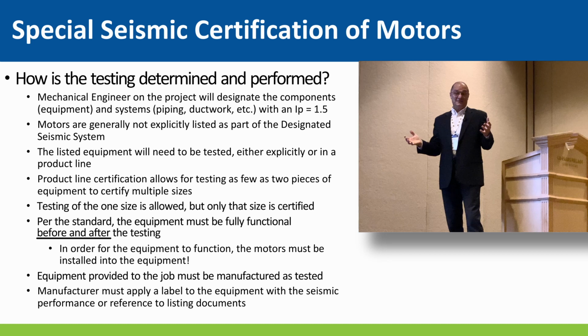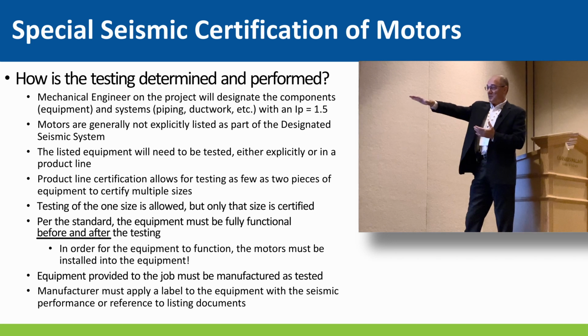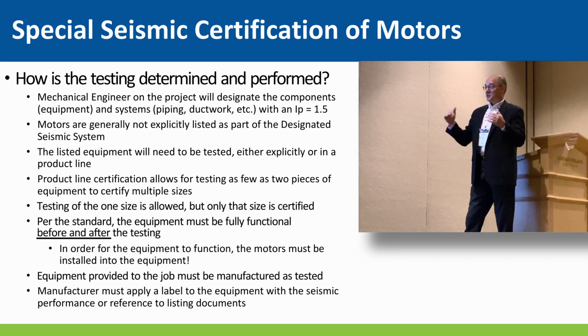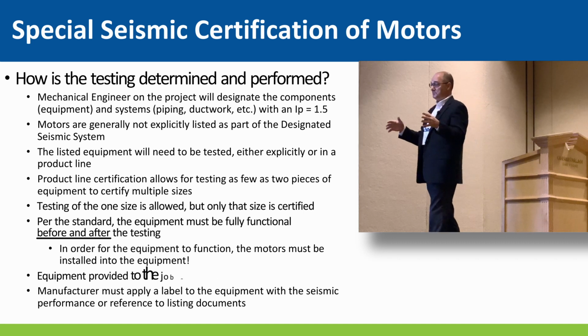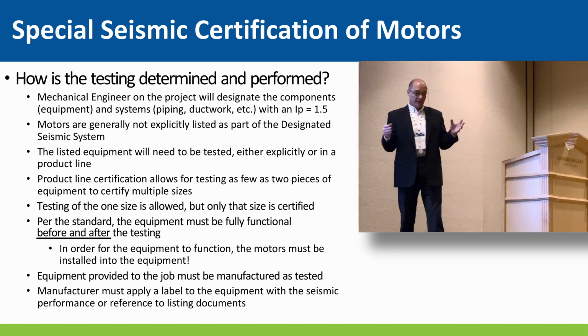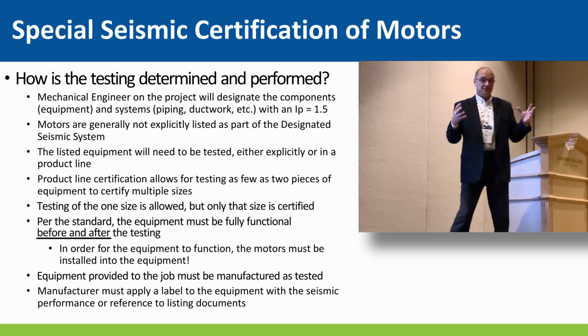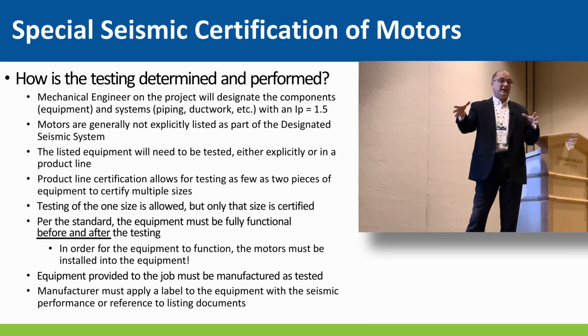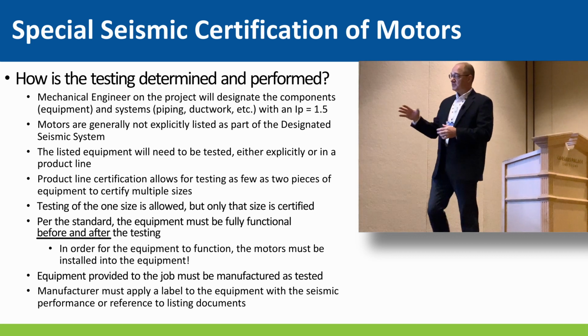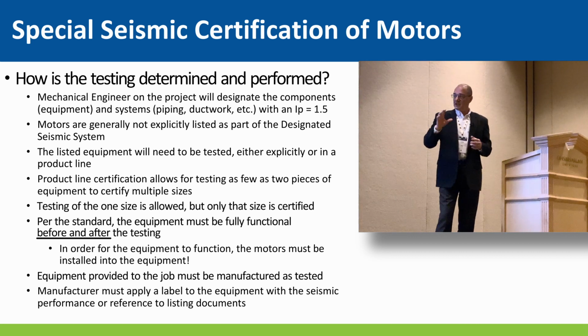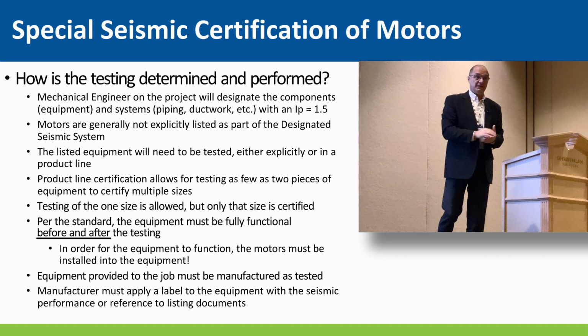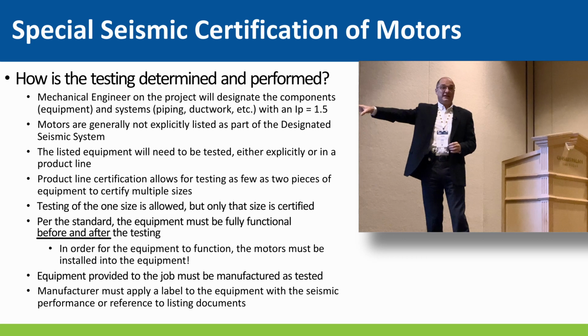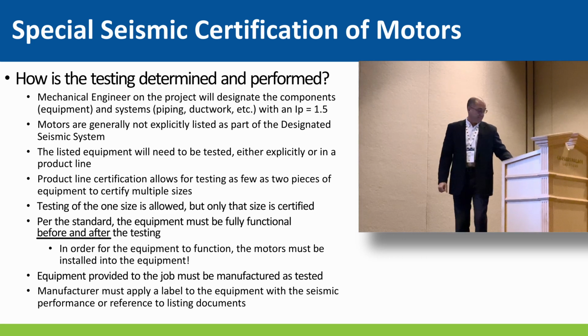So you have to think, do I have to test my motor? It depends. The motor must be installed in the equipment, and the equipment provided to the job must be manufactured as tested, or tested as manufactured. The way you build it in your factory is the way it has to be tested. Once that's done, the label gets applied to the equipment which has your motor in it. So your motor, even though it's part of the test, is not technically certified independently. It's certified as part of that equipment that has a label on it.